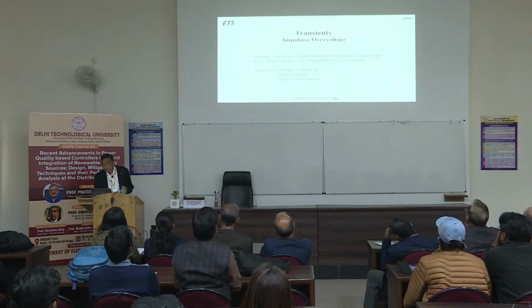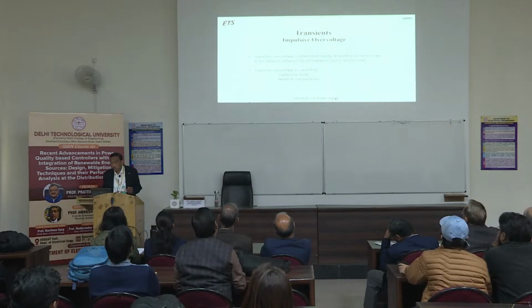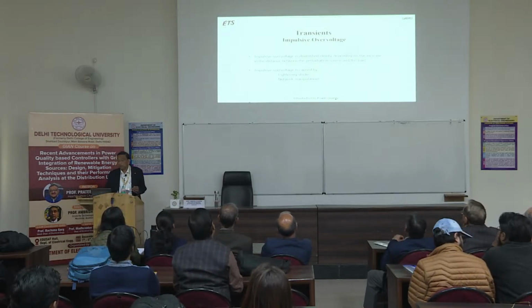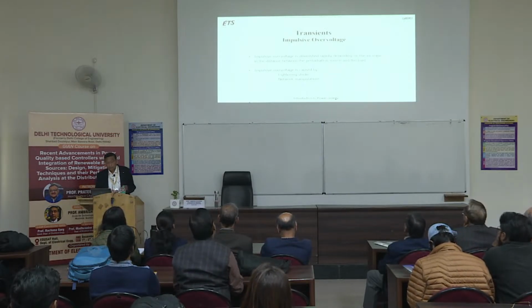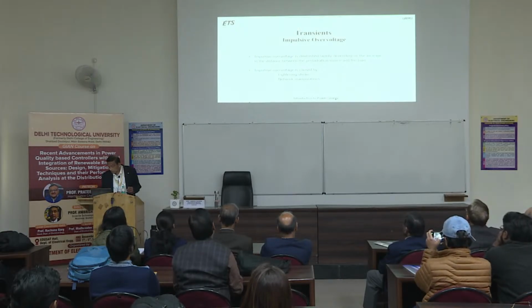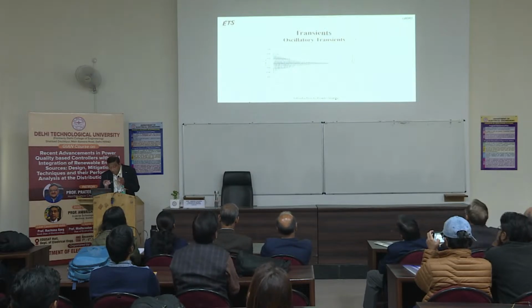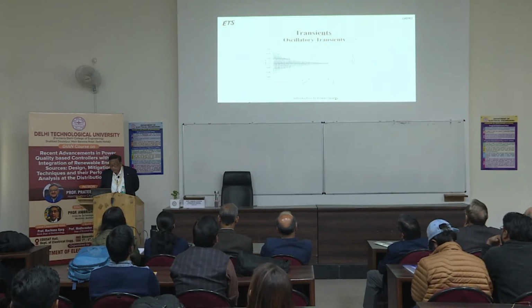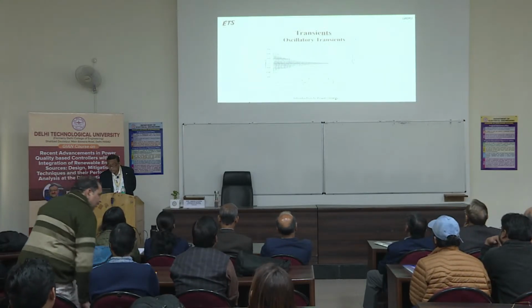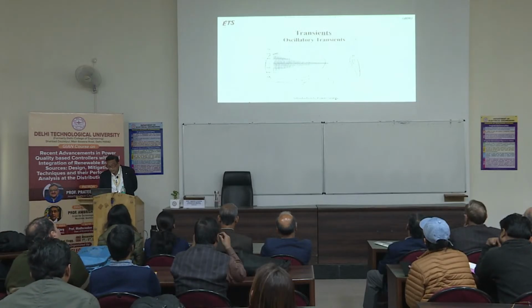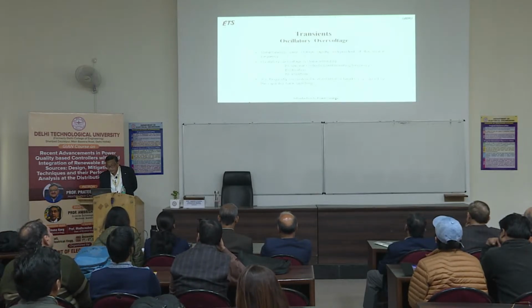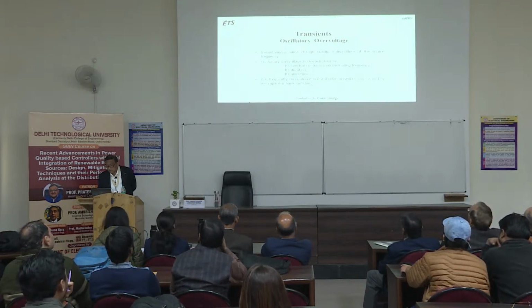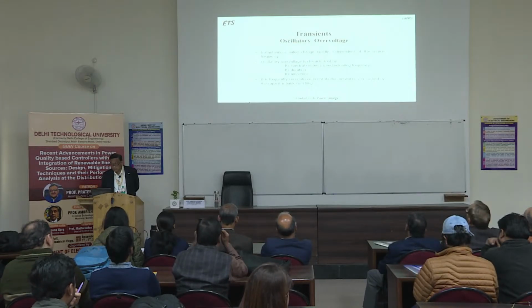Impulsive over voltage is diminished rapidly depending on the increase in the distance between the perturbation source and the load. Impulsive over voltage is caused by lightning stroke, network manipulations. Oscillatory transients, this is just an example of transient caused by capacitor switching, back-to-back capacitor switching. So you can see oscillatory transients are there, high frequency oscillatory transients. Instantaneous value change rapidly independent of the source frequency.